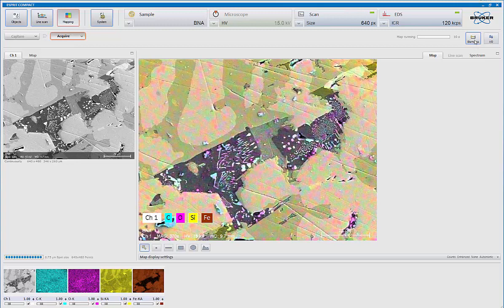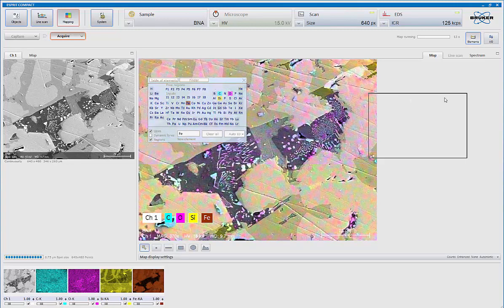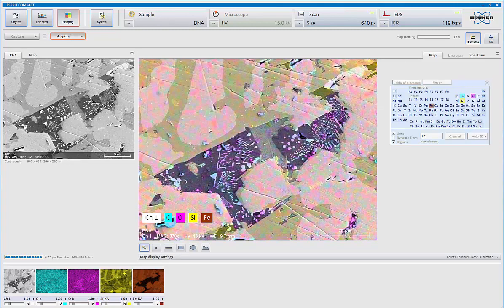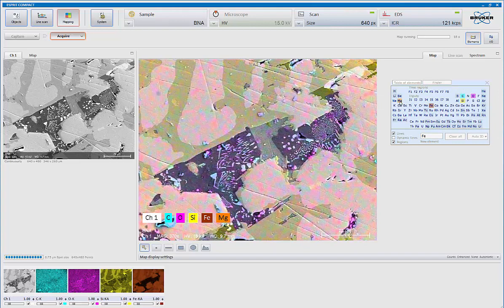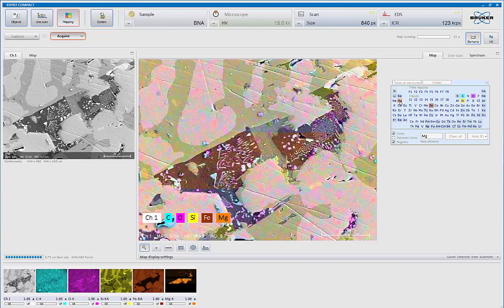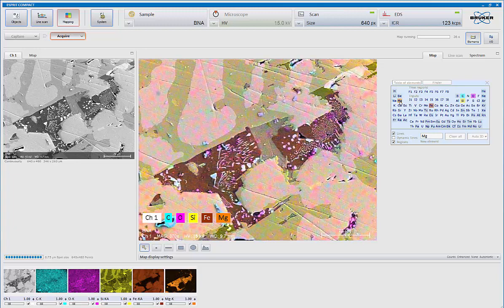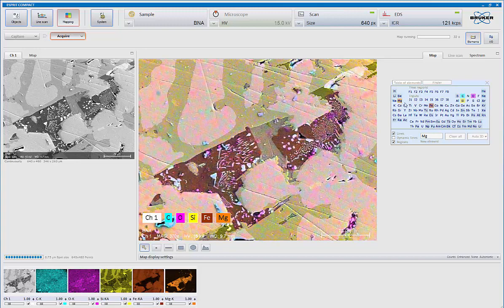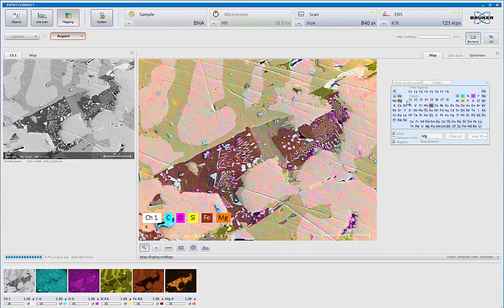At any point in time, I can bring up the periodic table tool and add additional elements, so for instance, I know I saw a magnesium phase earlier, I can click on that, and now that's being brought in. Whether I do it at the beginning of the map, during the map, or post-acquisition, I still get all the x-rays. We are collecting every single photon within this field of view, so you'd never sacrifice or lose any aspect of the system.